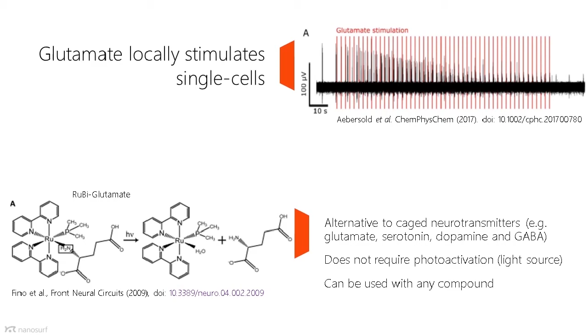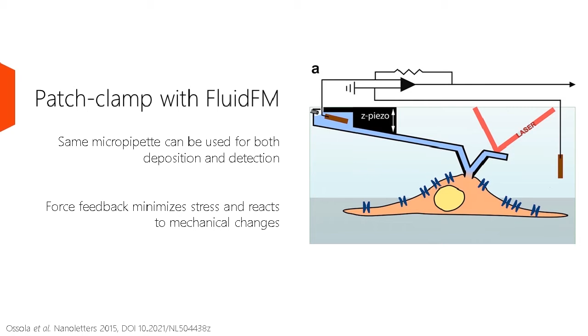Now, because the FluidFM probe is a microfluidic probe, we can actually use the probe itself to measure the action potential or voltage-gated receptors directly. Added benefit is that it's force sensitive. So if there's any physical changes to the cell during a patch, like if the cell contracts or swells, the probe will react, and we can maintain the ohmic seal on the patch. We can also measure physical changes to cells during voltage clamp pulses. So if a cell also reacts to a voltage pulse, then we can see that happen.